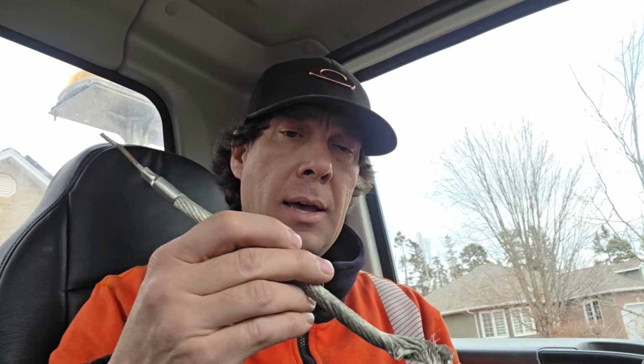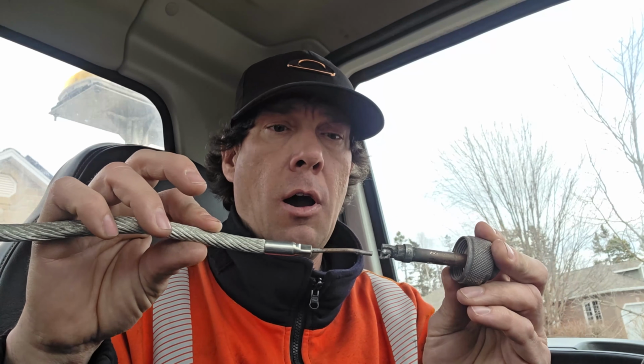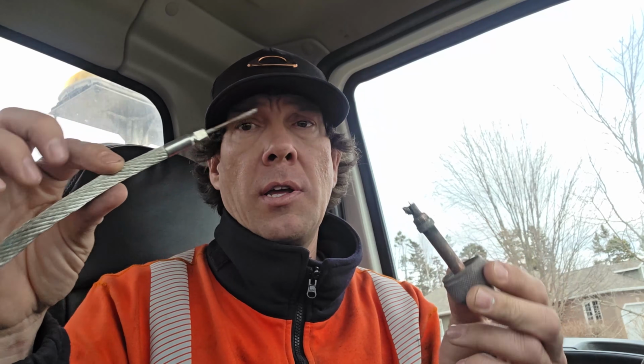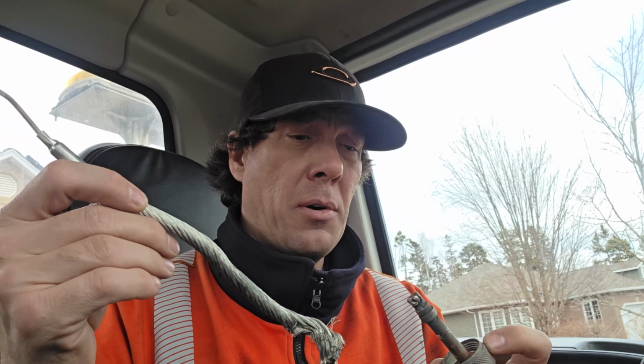Figured there could have been an arcing tap clamp. As that tap clamp arcs and the voltage goes down, due to the type of equipment inside the school, there could be increased current flow. That wouldn't cause a fuse to blow immediately, but after months and months of that, it can certainly melt a fuse off.